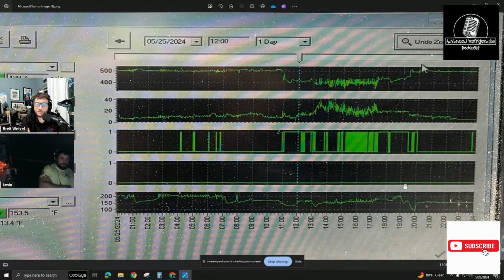The other thing I told him to do, I was like, if you know how, because there's not that many cases at a Schmaltzy's, right? So if you basically know that, okay, this case at 30% is able to achieve the superheat that it's supposed to, but you see another one that has a higher superheat and basically it's open to 60%, that's an indication that it might be giving false readings, and they should probably go downstairs and see what the hell's going on. You know what I mean?